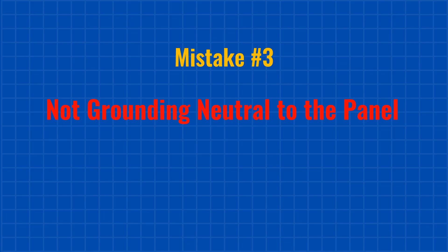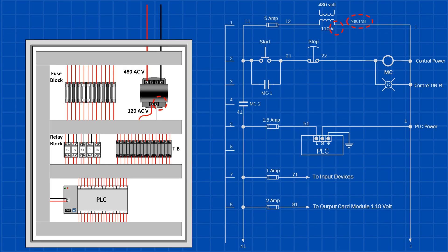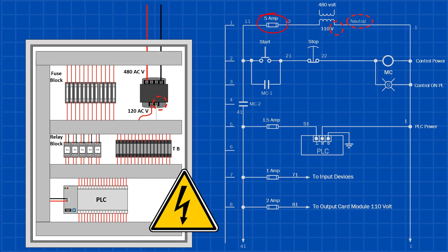Mistake number three. Not grounding the neutral to the panel. I've seen this mistake more than once, where the neutral on the secondary side of a control transformer isn't bonded to the panel and to the incoming ground. This creates both a safety hazard and a troubleshooting nightmare. Here's the issue. If the hot side of the control voltage shorts to the panel and the neutral isn't grounded, the control power fuse won't blow and the panel chassis can stay energized.